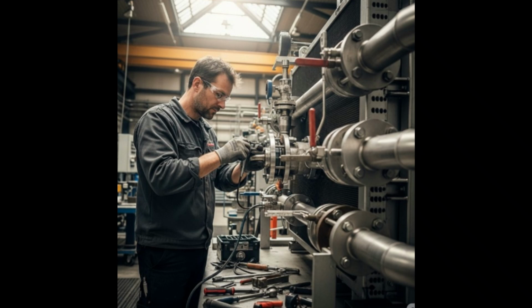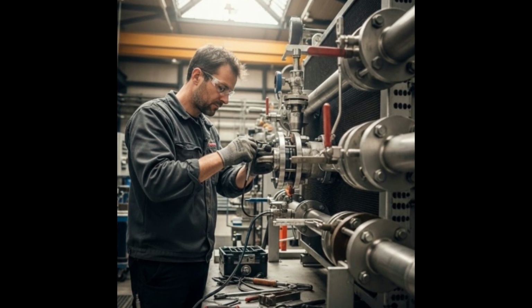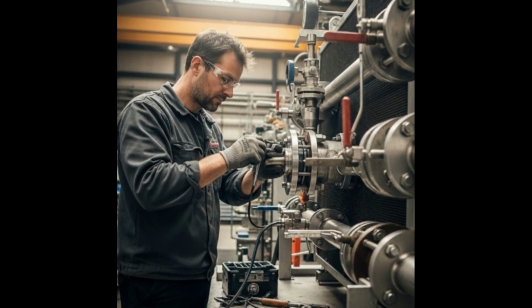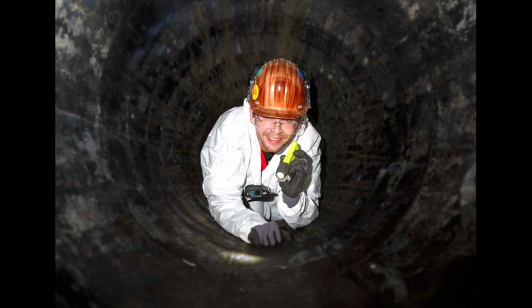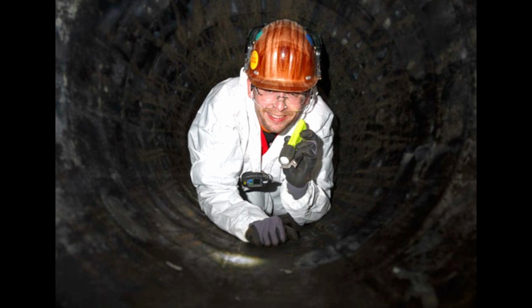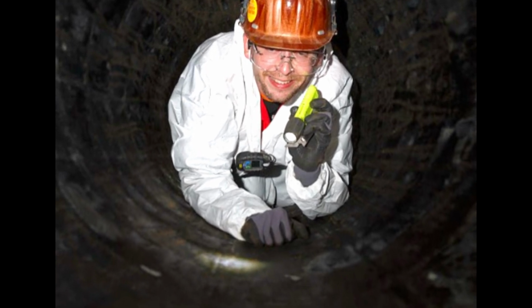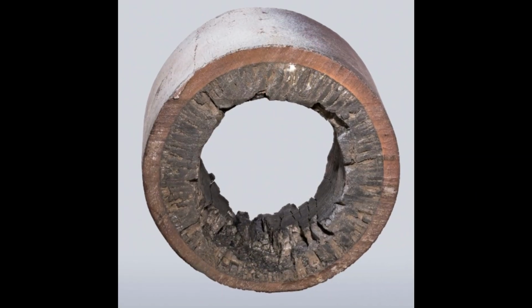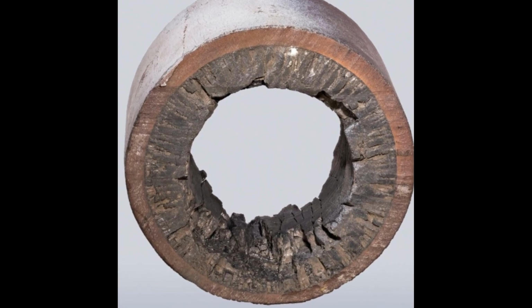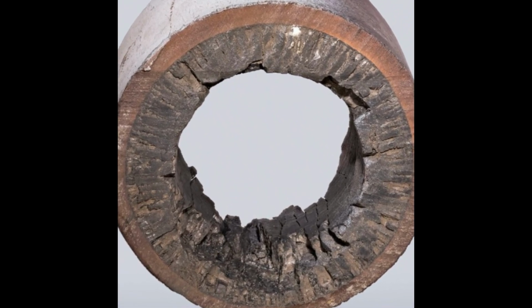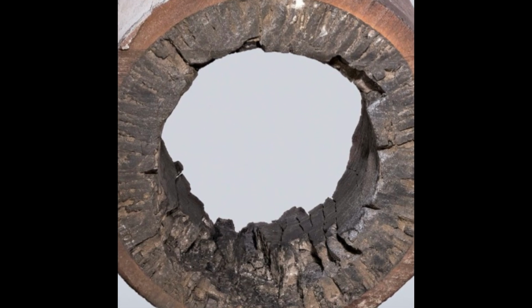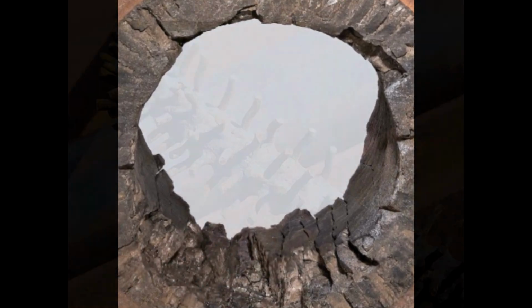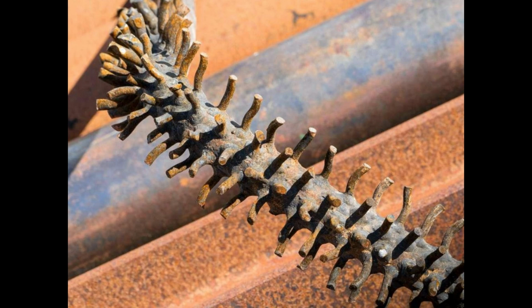Troubleshooting heat exchangers. Heat exchanger technicians face a variety of challenges, but a few problems are consistently at the top of the list. Fouling and scaling. This may be the most common and persistent problem. Fouling is the accumulation of unwanted material on the heat transfer surfaces. Symptoms are reduced heat transfer efficiency and pressure drop. Corrosion and mechanical failure.